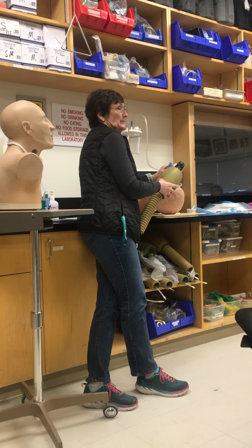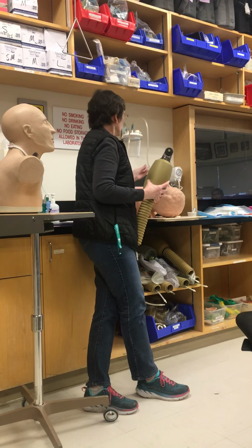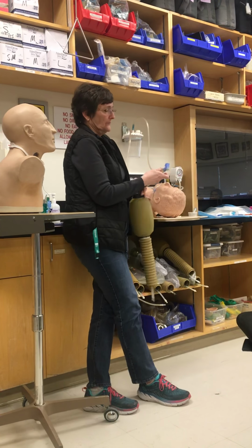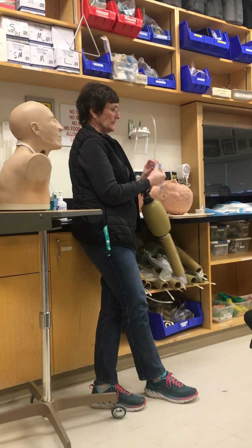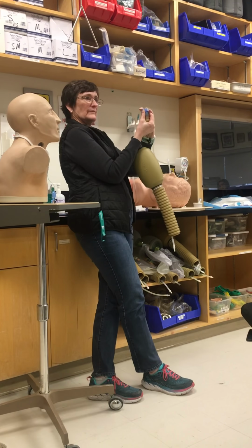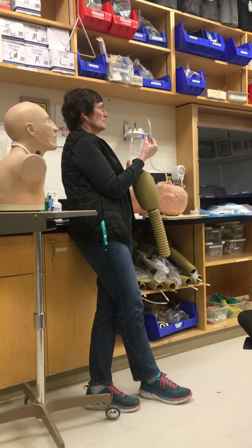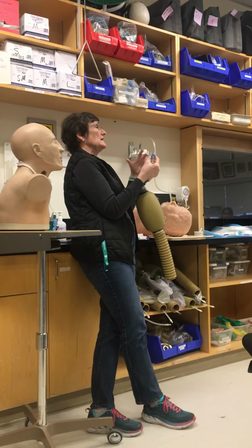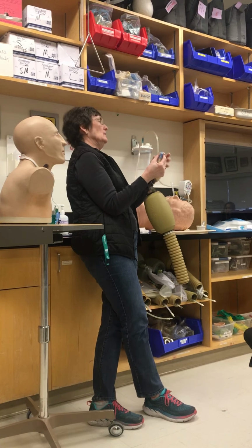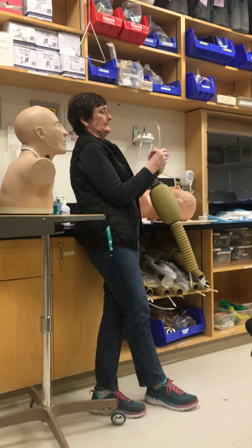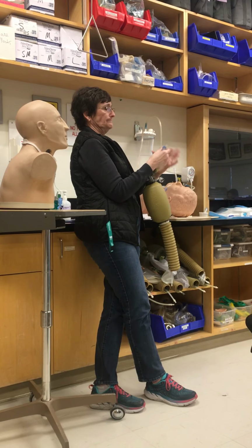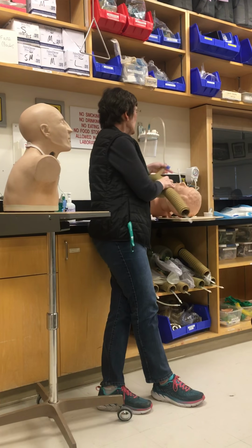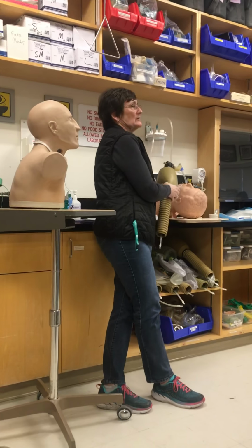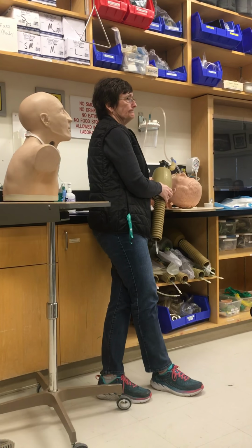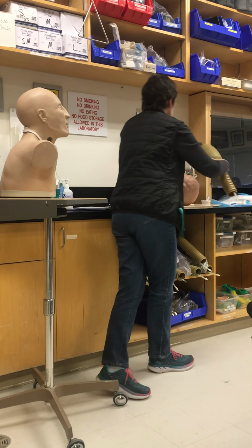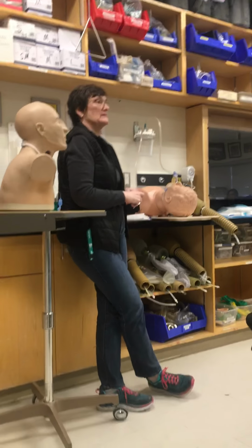So this PEEP keep adapter, let go of the bagger. On the end of it, when you pull off the cover, it's got a little one-way valve on it. When you put the suction catheter through there, it blocks it so that you're still maintaining the PEEP in the system, hence PEEP keep. That's why it's called that. So that's your PEEP keep adapter. If you are bagging a patient who is supposed to be on PEEP, this would be the best adapter to use for that.